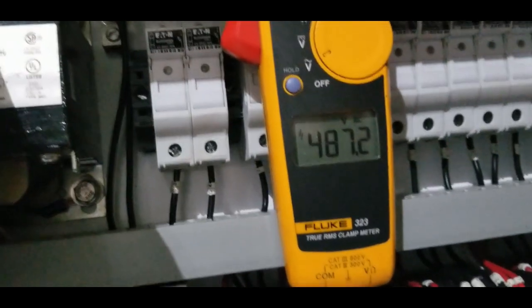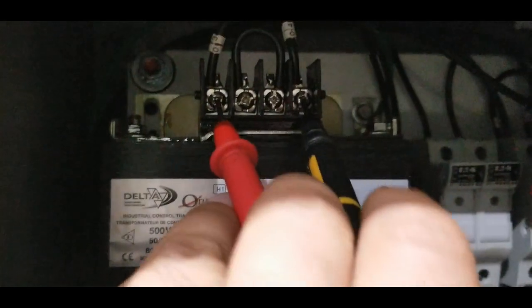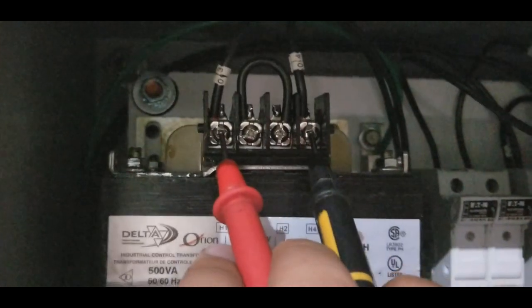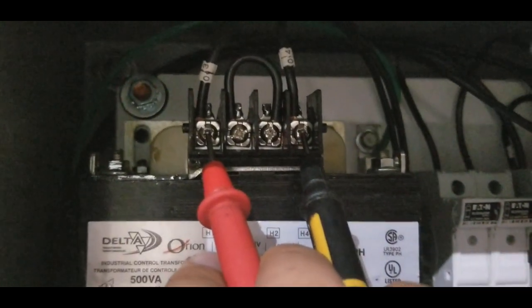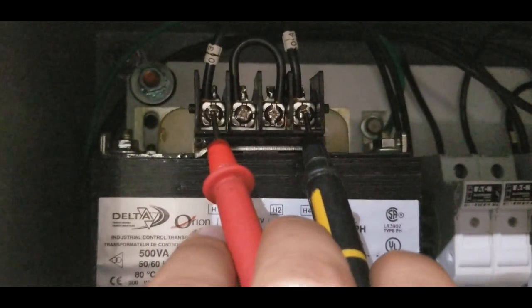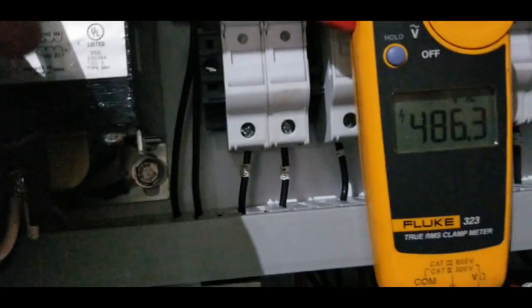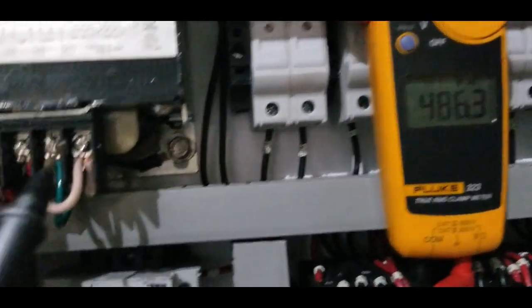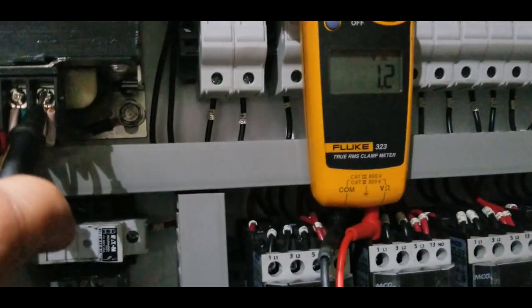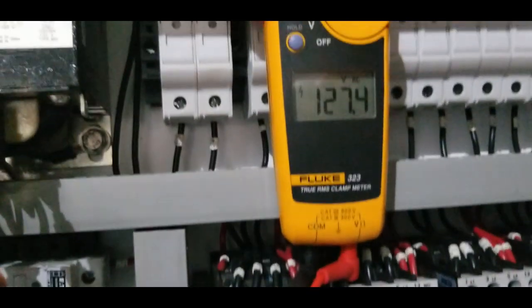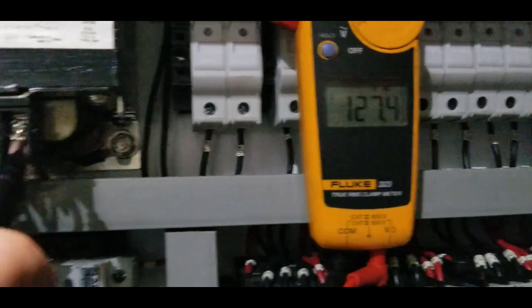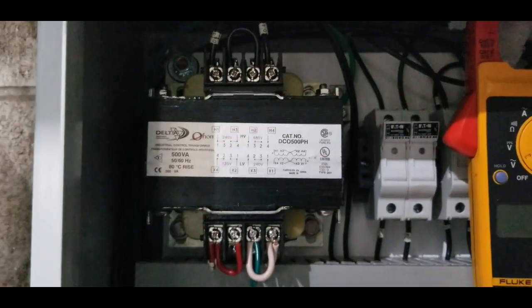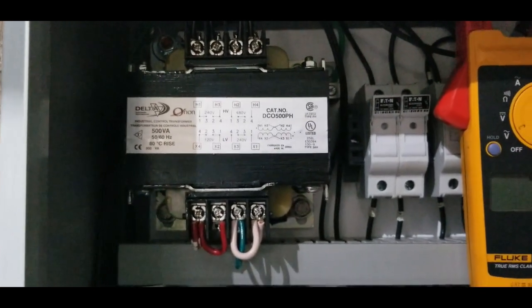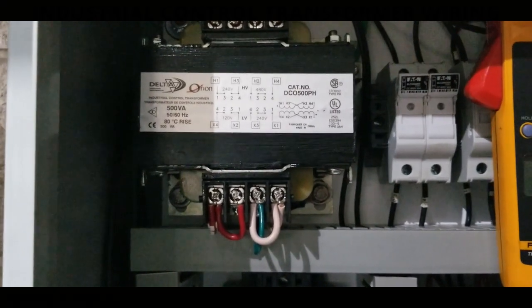Now you can see when I put my probe on the H1 and H4 terminals, I'm getting a reading of 480 volts. So that's our main 480 voltage coming to the transformer, and you can see H2 and H3 jumpered together. So that's our 480 coming to the transformer on the primary side. Let's check our secondary side. On the secondary side, I'm going to put my multimeter probes on X4 and X1. You can see I'm getting a reading of 120 volts AC. So that's how the transformer is wired.